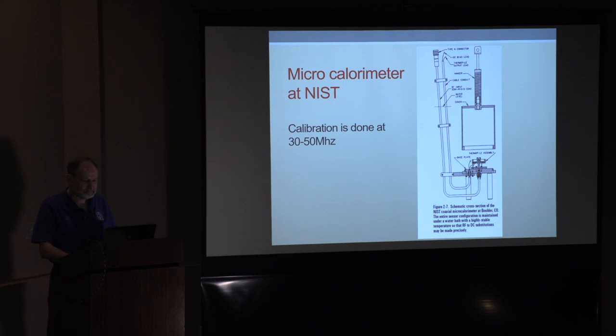And the calibration is done at 30 to 50 megahertz because SWR is less of a factor at 30 to 50 megahertz. The calibration of attenuators is, at least according to PRD, pretty much the same at DC as it is at 30 to 50 megahertz. And line loss is lower, and so your uncertainty list gets much smaller if you keep the frequency lower. And of course, as you know, when you plug in an HP power head, there's a frequency versus calibration table that says how to compensate for some of the differences at higher frequencies.